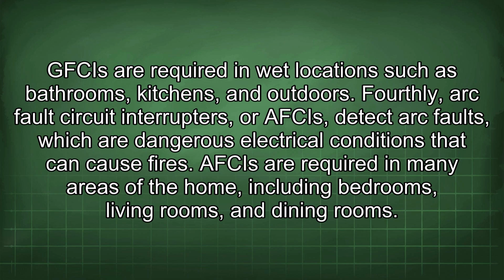GFCIs are required in wet locations such as bathrooms, kitchens, and outdoors. Fourthly, arc fault circuit interrupters, or AFCIs, detect arc faults, which are dangerous electrical conditions that can cause fires. AFCIs are required in many areas of the home, including bedrooms, living rooms, and dining rooms.